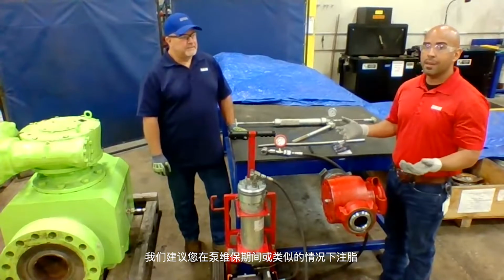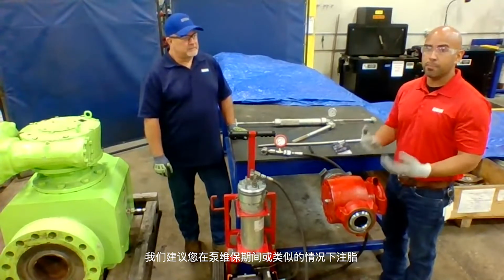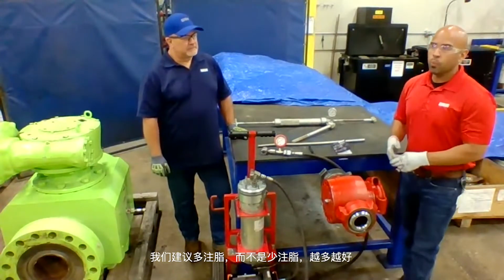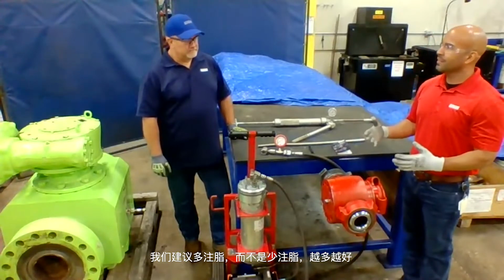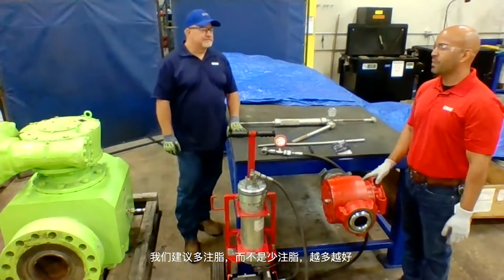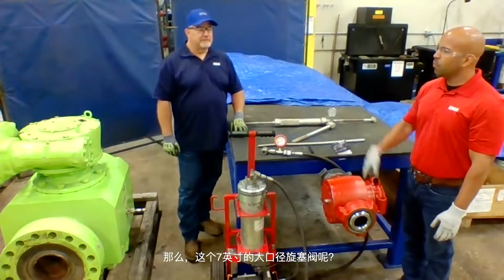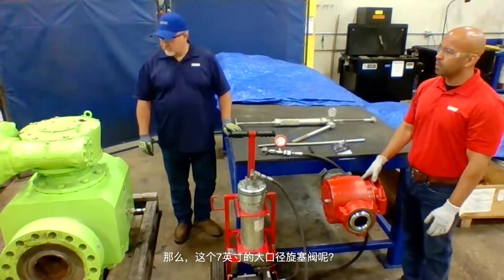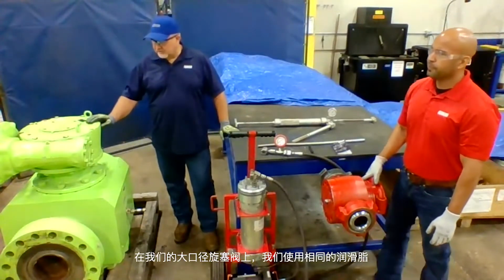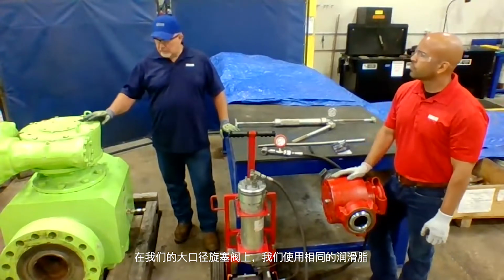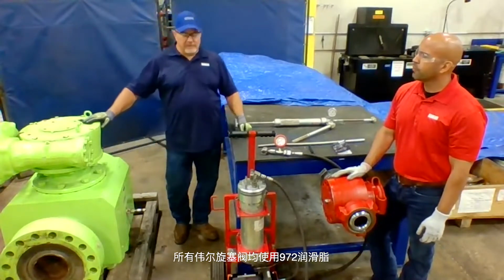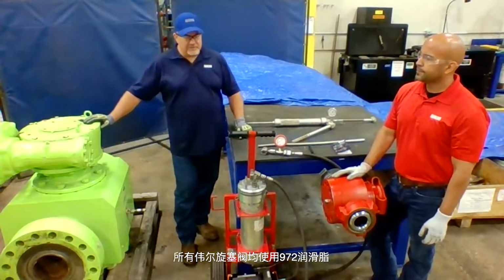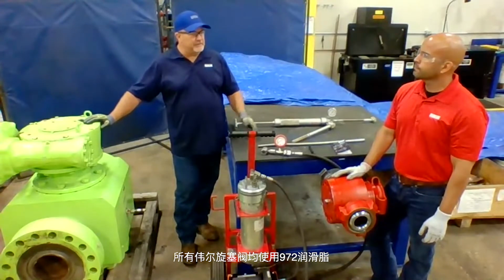We do recommend that you grease in between stages during pump maintenance or anything like that. We always recommend more greasing rather than less. More is better. Yeah, more is better. All right, but what about this 7-inch large bore plug valve? On our large bore plug valve, we use the same grease. All Weir plug valves are engineered around the use of 972 grease.